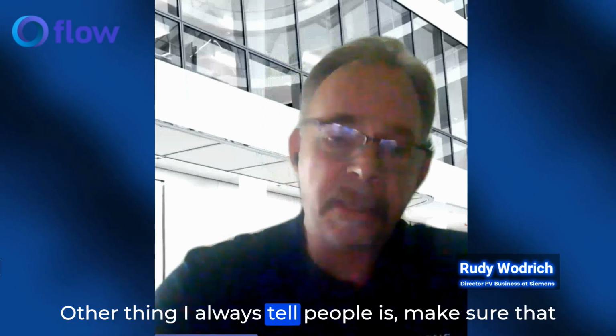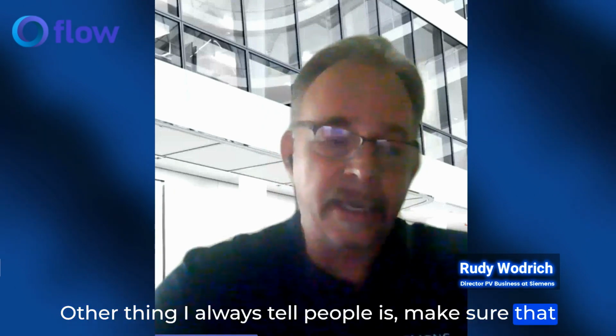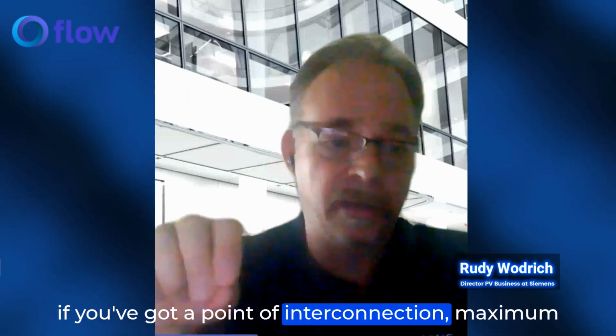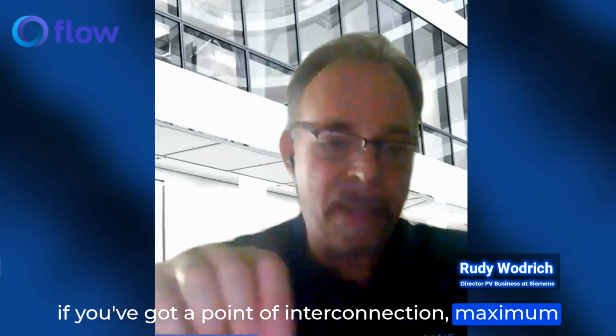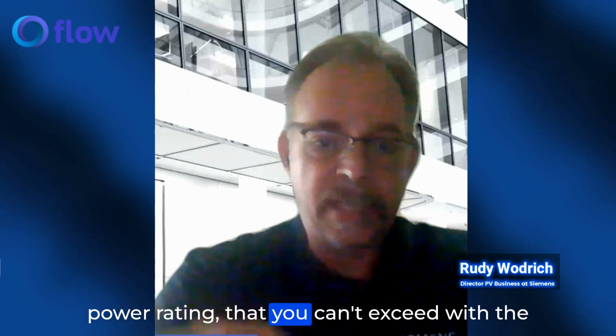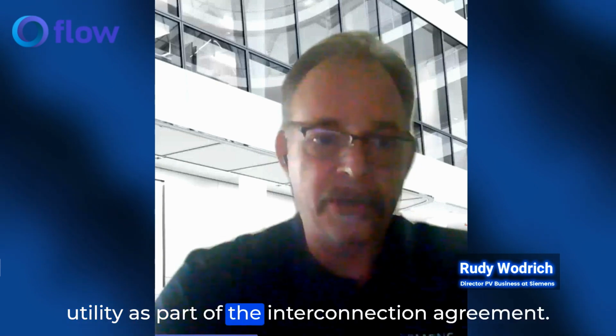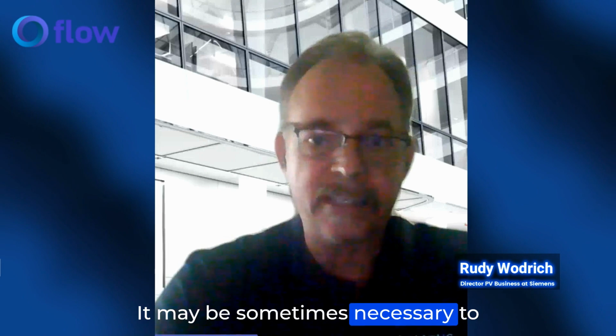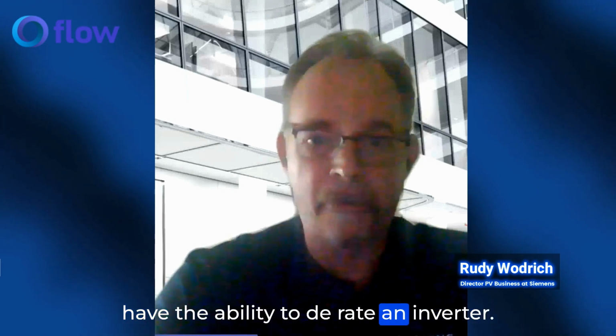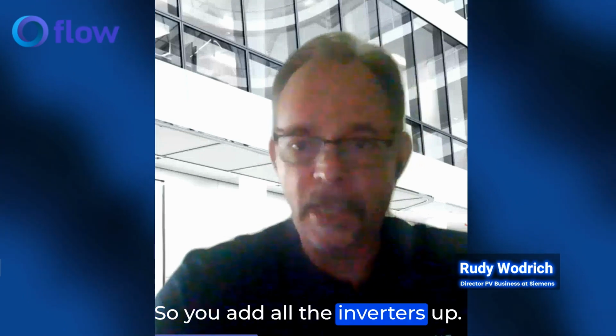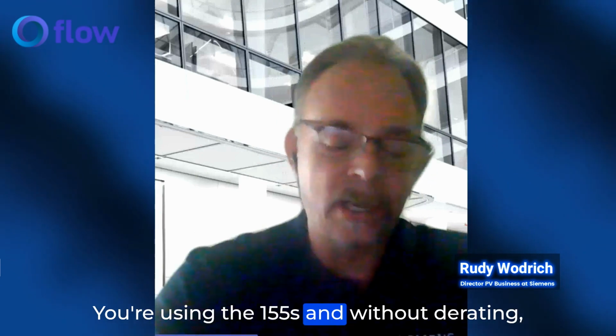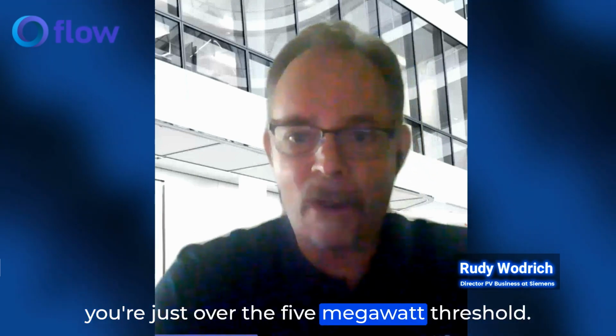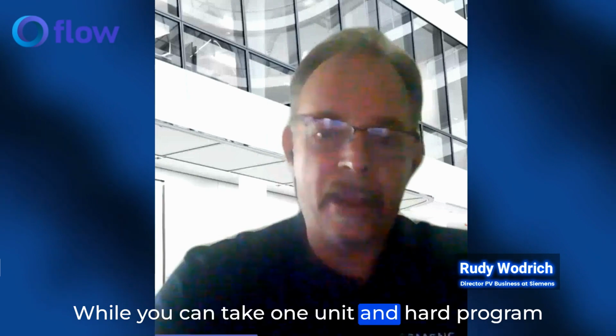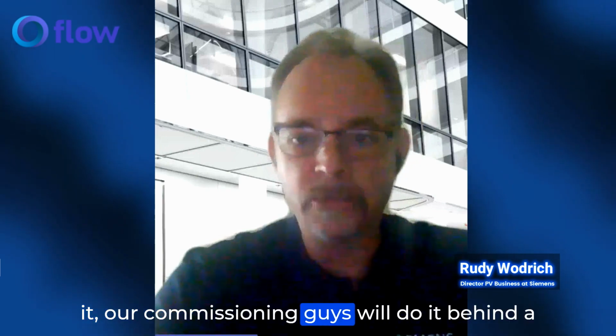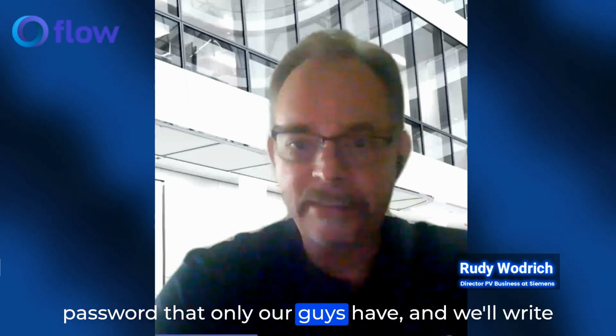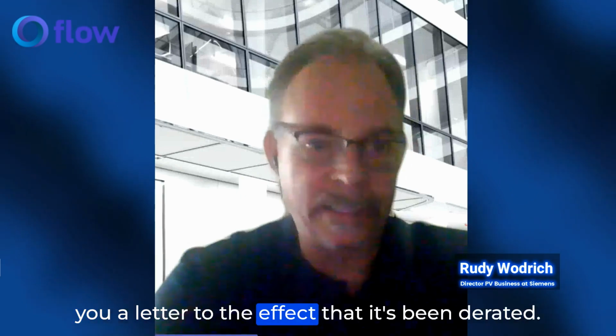Other thing I always tell people is make sure that if you've got a point of interconnection maximum power rating that you can't exceed with the utility as part of your interconnection agreement, it may be sometimes necessary to have the ability to derate an inverter. So you add all the inverters up, you're using the 155s, and without derating, you're just over the 5 megawatt threshold. Well, you can take one unit and hard program it. Our commissioning guys will do it behind a password that only our guys have, and we'll write you a letter to the effect that it's been derated.